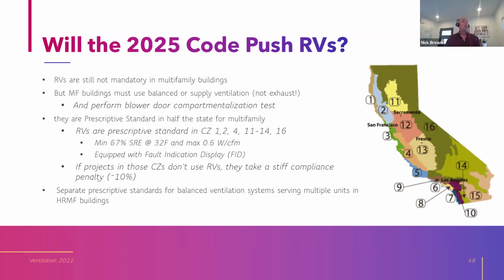Okay. And in these climate zones, and notice they added 4 and subtracted 15, because it's 1, 2, 4, 11 through 14, and 16. Same thing, recovery is going to be prescriptive standard in more than half the state for these buildings. And the systems need to be equipped with a fault indication display, or FID, if complying prescriptively. Of course, if you comply via the performance method and your recovery ventilator doesn't come with an FID, you just check that box and you'll get dinged about 10% of your compliance credit, but you'll still get 90% of it. So I think this is really going to help adoption of recovery ventilators.